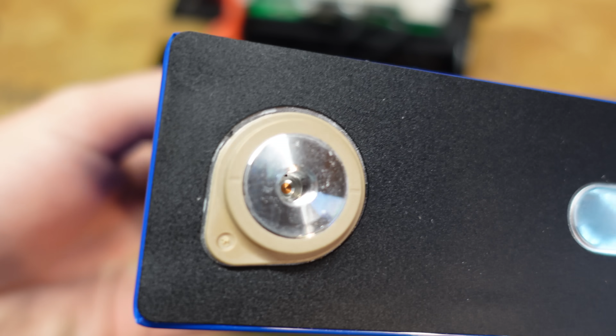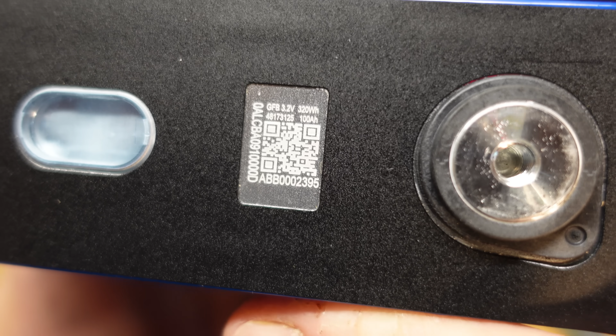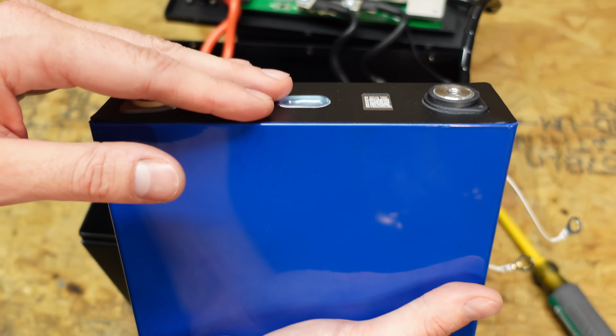Here's the cell itself, you can see a close-up look at the terminals. They all look good, don't show signs of being used other than the single time it was assembled in this enclosure. QR code is intact, and it specs out 100 amp hour, 320 watt if I'm reading that correctly, and it says GFB, so maybe GFB is the brand name. I'm not familiar with it, but these are rated for 100 amp hours, which is pretty cool. Sometimes manufacturers will stick in like 105 amp hour and derate it to 100 amp hour because the cell is underperforming, or just to make sure you're getting actual rated capacity. But in this case, these cells are rated for 100 amp hour, and they tested at 102 amp hour, so that is fantastic.